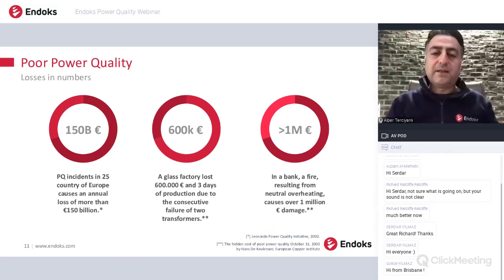there's a continuous operation in a facility, this power quality becomes very, very important. Textile, paper, and of course, semiconductor industries, and all critical industries having continuous operation. Any malfunctioning of any motor drive, or tripping of any motor drive in this continuous process, may cause interruptions. And the bad thing is that all the raw material becomes scrap. So the industrial facilities lose money and time if there's a failure because of power quality. On the other hand, for example, in a bank, a fire resulting from neutral overheating caused over €1 million damage.